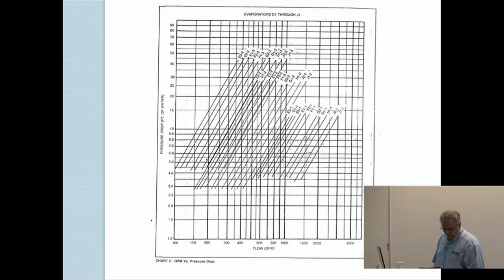Now, just for what it's worth, most manufacturers list their pressure drops in foot of water, but most gauges are in PSI. So 1 PSI is equal to 2.31 foot of water, if you want to make a note of that. Again, 1 PSI is equal to 2.31 foot of water. And conversely, 1 foot of water is equal to 0.433 PSI.